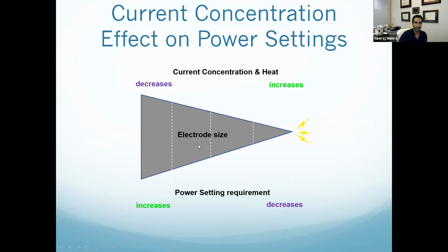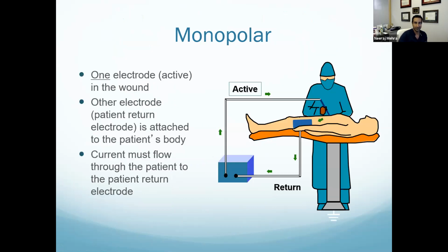So as your electrode size decreases, your power setting requirement increases. So how does this play out in a monopolar circuit? The thing you have to remember is that in a monopolar circuit, electrons are flowing through the patient this whole time. So why does the tissue destruction happen at the end of our instrument, our electrode, and not elsewhere?